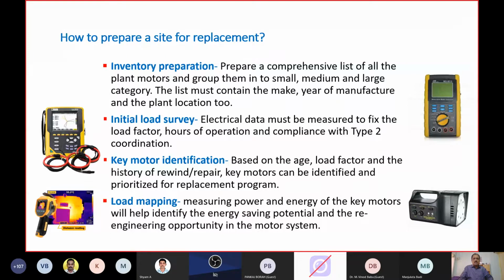So that would include the number of rewinds, repairs, number of hours of operation, load factor, and so on. So a key motor, once it is identified, can be a candidate for replacement upfront, whereas you would further want to explore how this can give you the return on investment, and therefore we recommend load mapping. For load mapping alone, on a reduced key motors list, you can invite external auditors like us. We can come and do load mapping or complete profile mapping and give you a final list which you can use for undertaking large-scale implementation of IE3 motors.